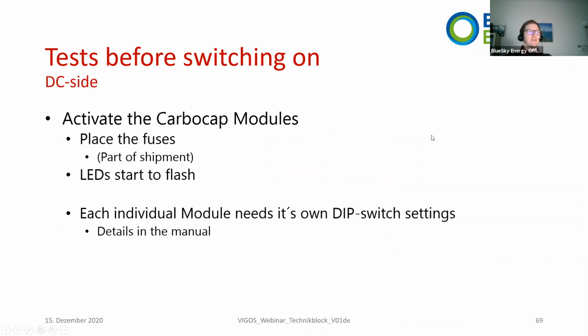As soon as you've done that, you can activate each CarboCap module. They don't give power or voltage by themselves. They need to be activated separately. First you place the fuses inside the module. They are part of the shipment, and then LEDs start to flash. You just need to wait 2 seconds, and then you can start the module by changing the configuration of the dip switch. Details you can also find in the manual.